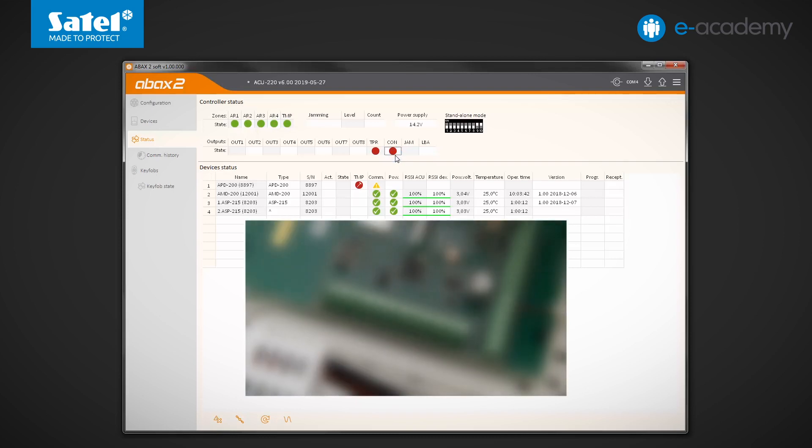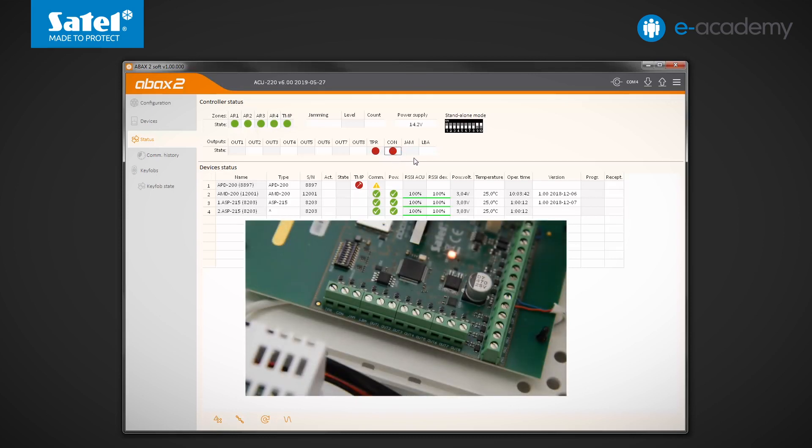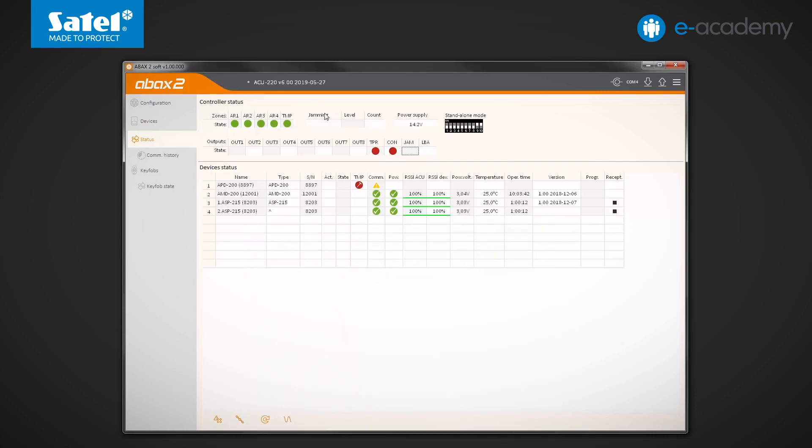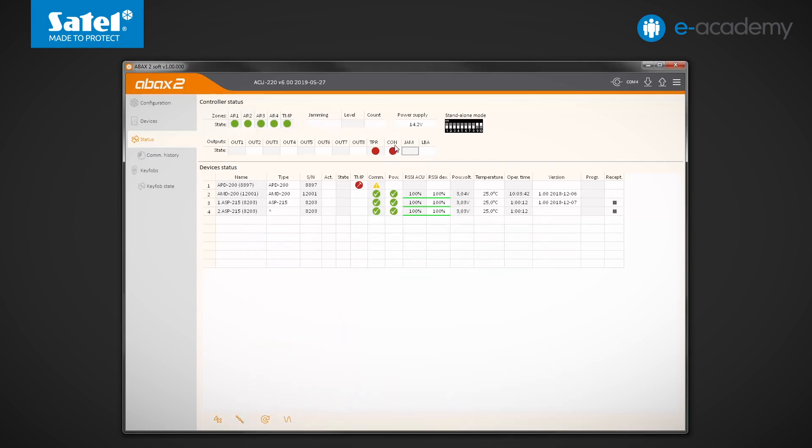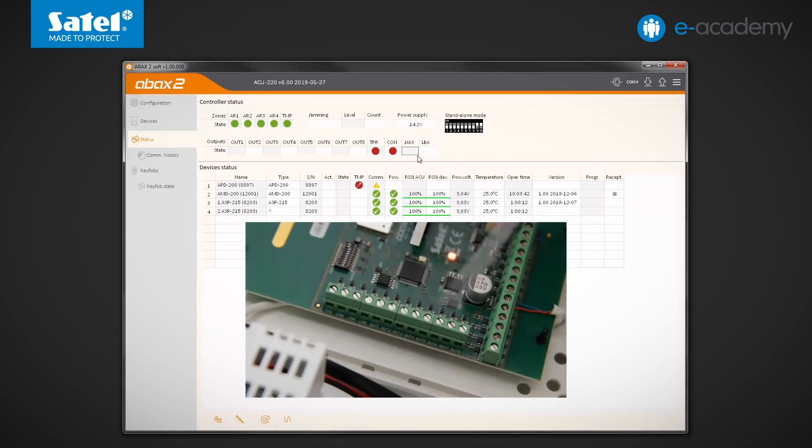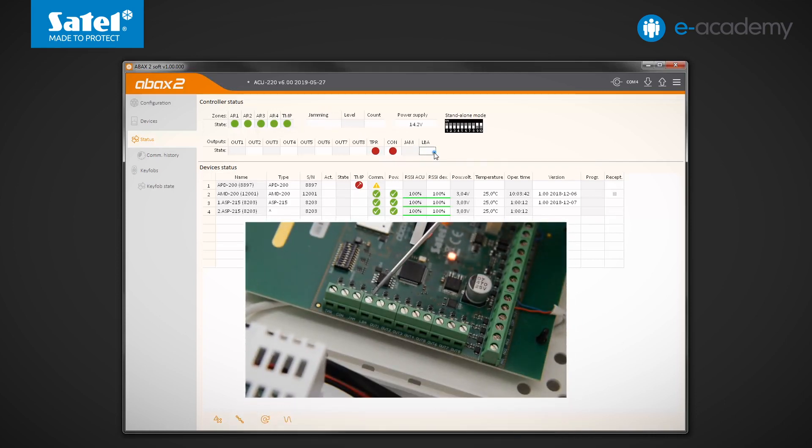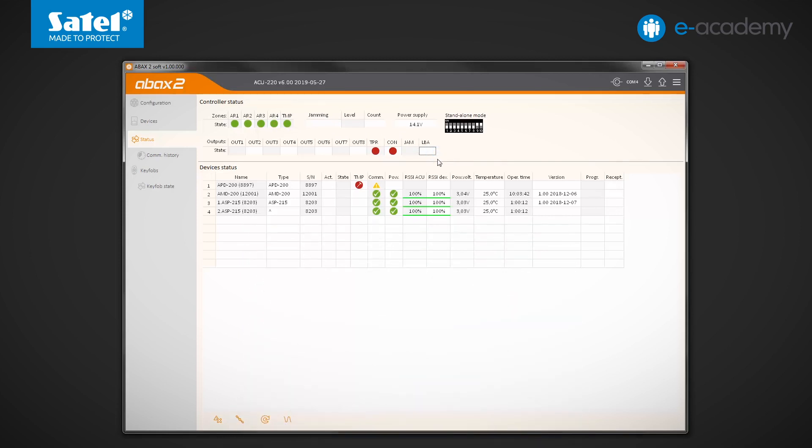The next output has already been mentioned. Designated as jam, it activates when the controller detects jamming of radio communication. The last output is LBA. It informs you about the power problems in the wireless system. It activates when the battery voltage of any of the devices drops below a certain level or when there are irregularities with the power supply of ACX220 expanders or ARU200 retransmitters registered in the controller.